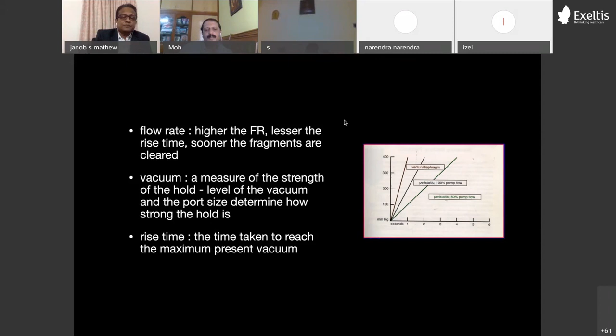So these are some of the terms that you should know. I've mentioned surge. Surge is what happens to the anterior chamber. There's a sudden collapse. There's a negative pressure as the occlusion breaks, and the whole of the vacuum at that particular point of time acts at the tip of the probe, and then the fluid in the anterior chamber suddenly gets sucked out, and the AC tends to collapse. That is called surge, and that is where you're scared of getting a PC rent.